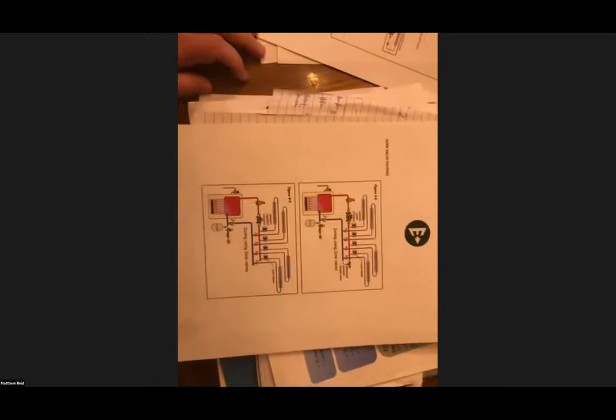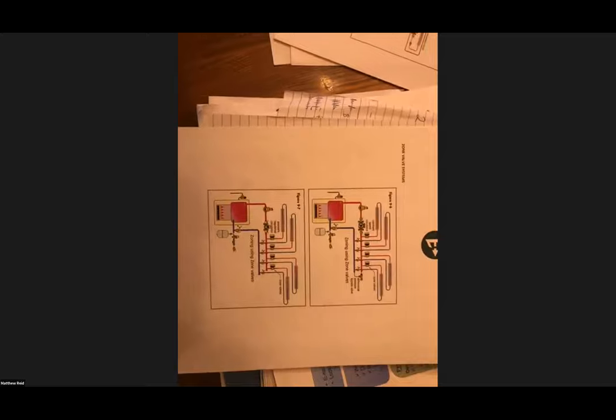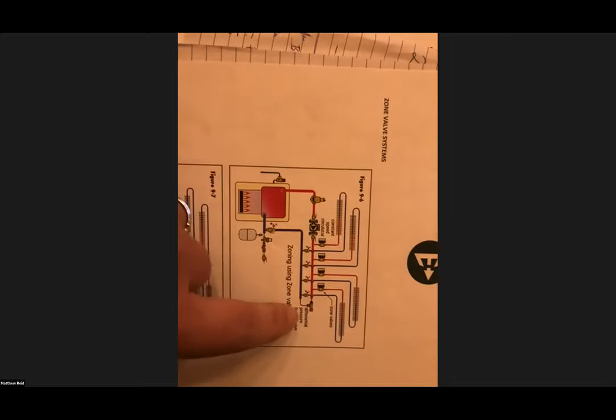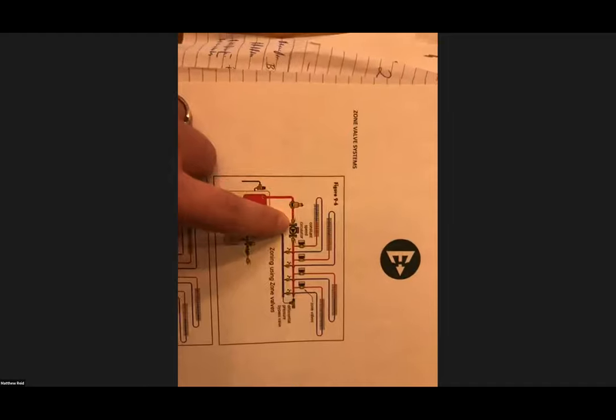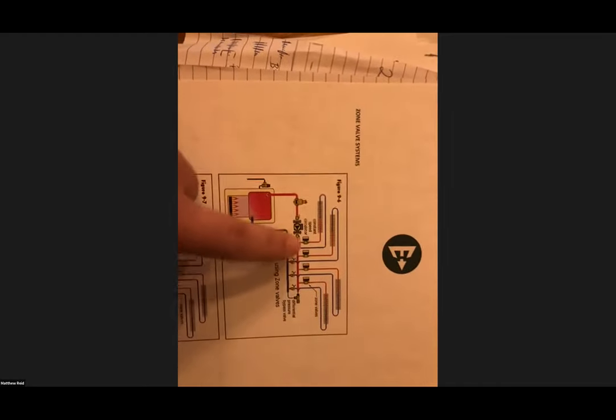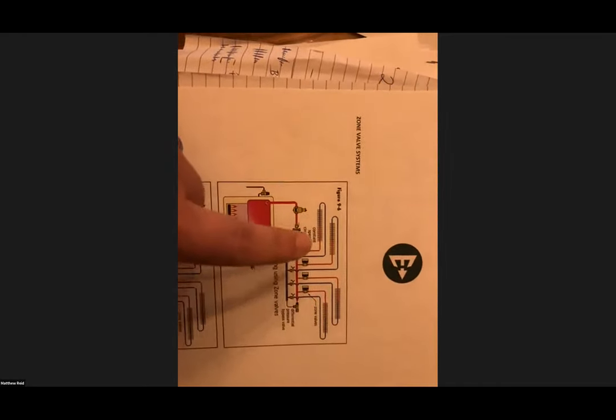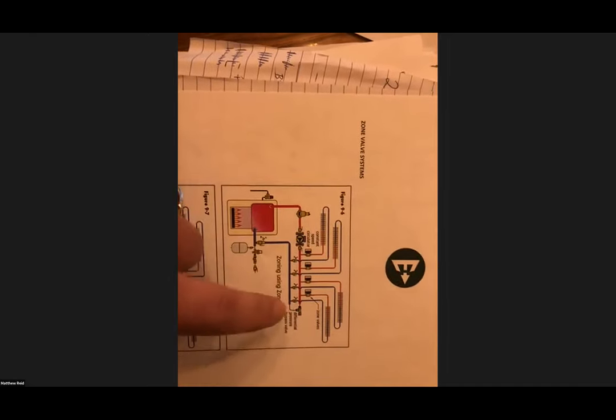Here's a very similar system as well, but now we're getting into a different type of piping system. We have our primary loop going up. We have a pressure-activated bypass because we're zoning with zone valves in this case. Now, this circ pump is going to be designed to handle all these zones at max flow. But as these zones close off, if they get satisfied, this pump is not going to be able to slow down. So you need the pressure-activated bypass.